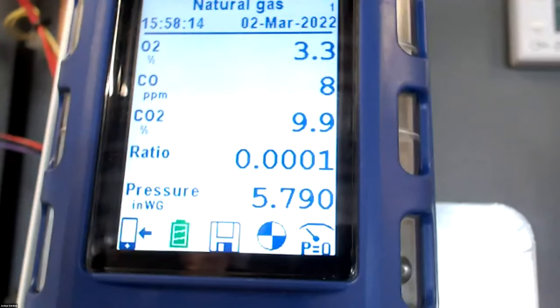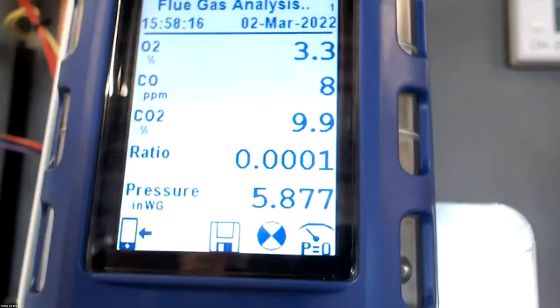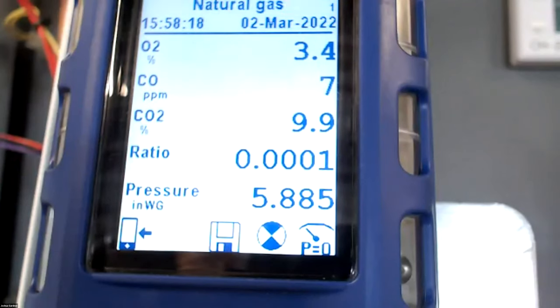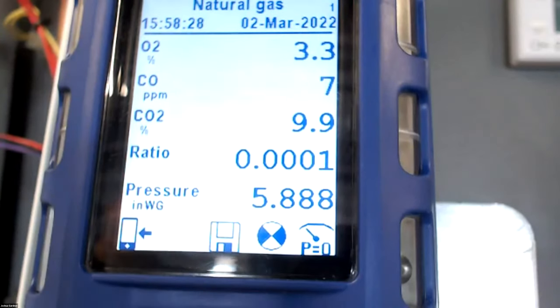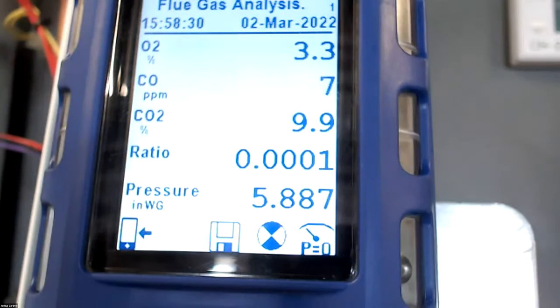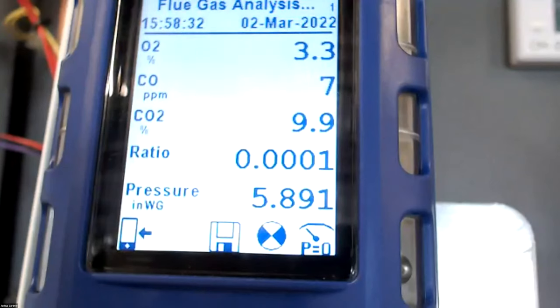All right. It looks like we planed out at 3.3 on our O2, 3.4. And we need to be between 3 and 4.5. We're there. CO needs to be below 10. We're good. And our CO2 needs to be between 9 and 10, and we're right about there.